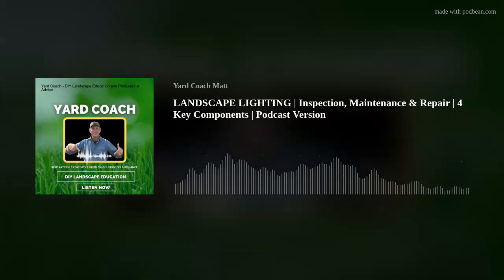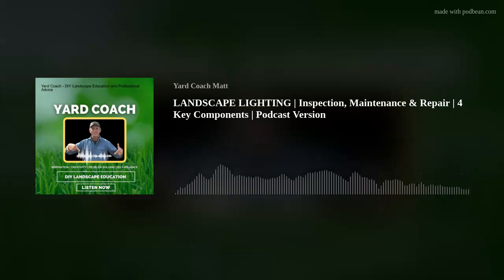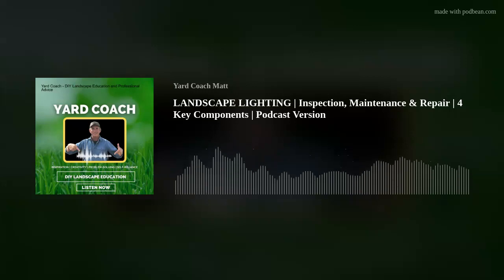So where do we start? Replace the bulb and check. Put the new bulb in. Does it work? Perfect. If it is not, then we've got to check the wiring of the fixture. How is it wired to the cabling? Is it still good? Or did something come apart? Is it really corroded because it got shoved in the ground with no sort of protection? Did they use the wrong kind of wire nuts instead of a grease sealed one? Repair and then recheck. Eventually, you're going to find the culprit.